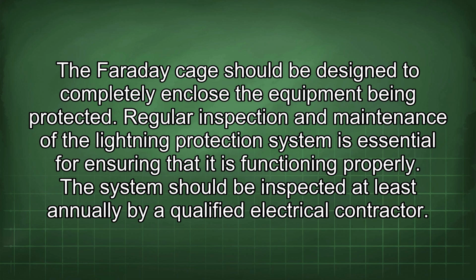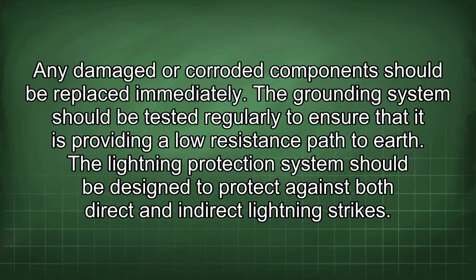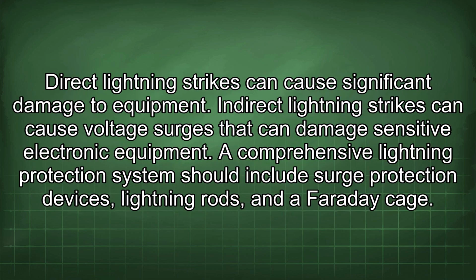Regular inspection and maintenance of the lightning protection system is essential for ensuring that it is functioning properly. The system should be inspected at least annually by a qualified electrical contractor. Any damaged or corroded component should be replaced immediately. The grounding system should be tested regularly to ensure that it is providing a low resistance path to earth. The lightning protection system should be designed to protect against both direct and indirect lightning strikes. Direct lightning strikes can cause significant damage to equipment. Indirect lightning strikes can cause voltage surges that can damage sensitive electronic equipment.